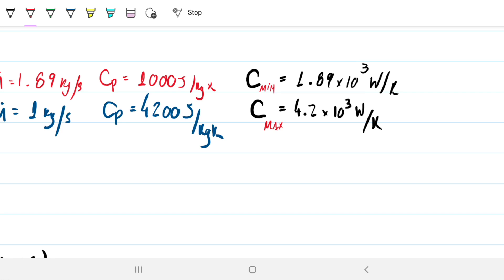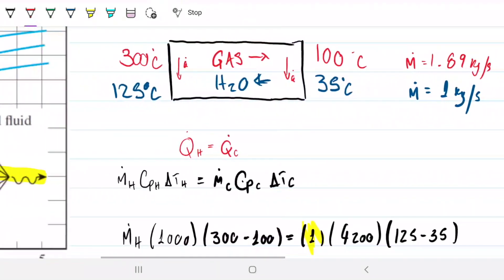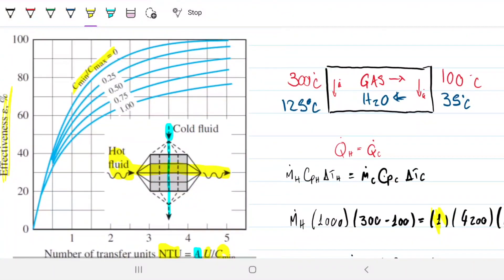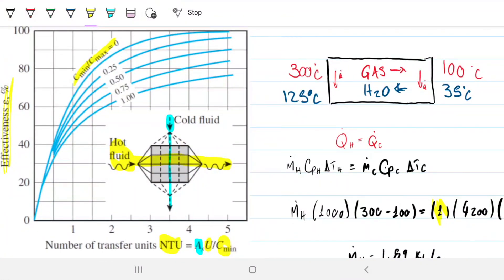If you guys recall, our NTU method, what we're trying to find is the area. So to find area, we need the overall heat transfer coefficient, which we have already. We need the capacity rate, the smallest one, which we have already, and we need the number of transfer units, which we don't have. So if you want to find the number of transfer units, we're going to be using this graph for which we need the ratio between the capacity rates and the effectiveness.